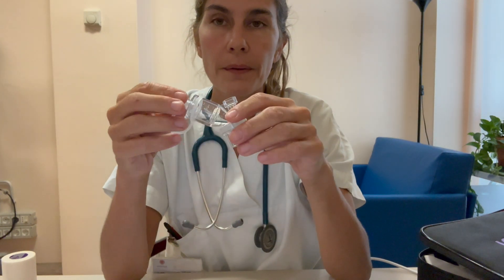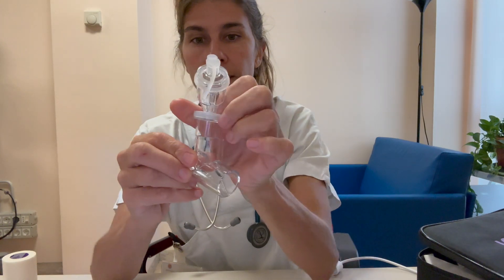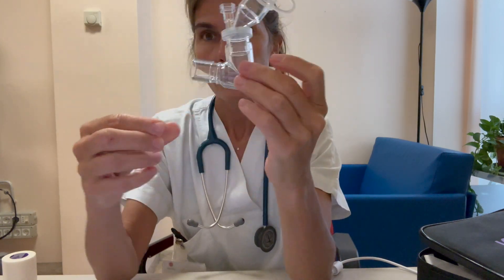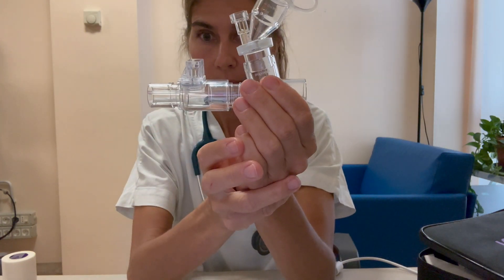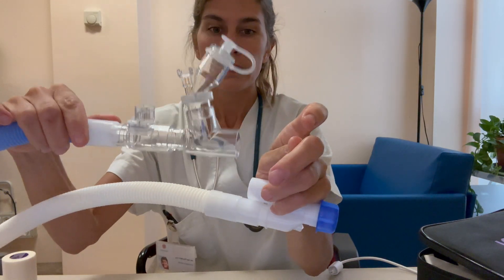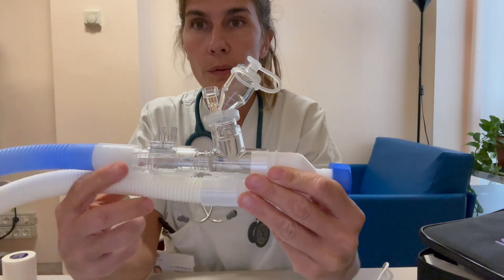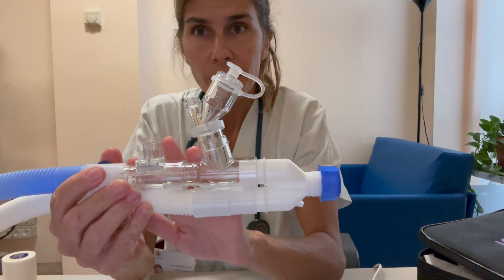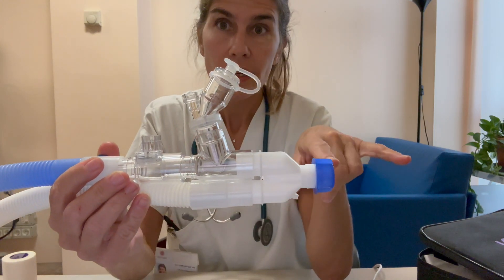Using AeroICU Max Plus is really simple. For example, if we are under NIV, you connect this medication cup to this connector. Then you connect all this into the flow sensor and all this into the inspiratory limb before the Y, so you don't need to worry about leaving this even when not doing the aerosol, because this counts as compressible volume and not an instrumental dead space.